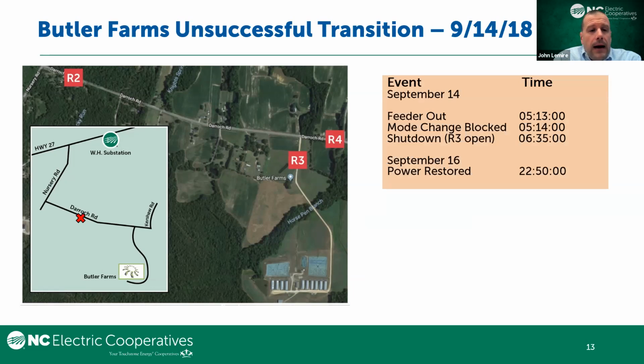You can see on the map we had a tree fall on the distribution line. The R's represent the reclosers, or the boundaries, where R3 down is where we support the farm, and between R2 and R4 is where we can support the feeder. So a tree fell within the feeder boundary, which means the microgrid should have come up and supported the farm until the tree was taken off of the line.